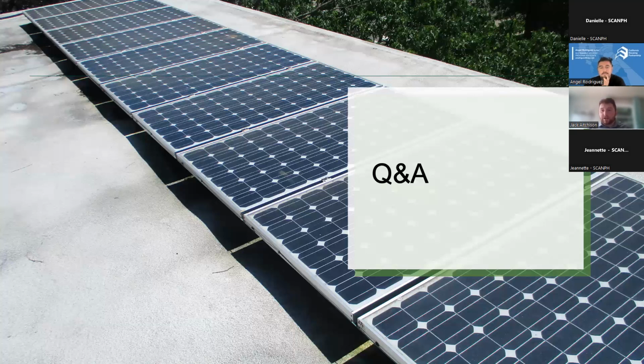The reason why heat pump water heaters have less recovery is not because it's a limit of the technology, it's a limit of electrical capacity. And so avoiding that, we could have a tankless heat pump that heats water just as fast as gas boilers, but the concern is the electric draw, the kilowatt draw, if you're subject to demand charges, as well as just capacity of electricity at the building. And so you really need to be considerate of that.